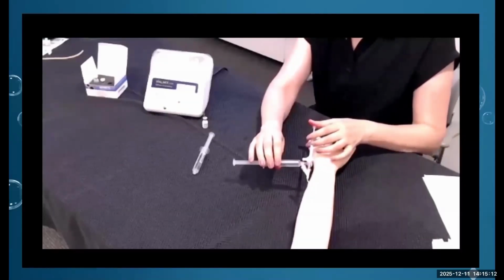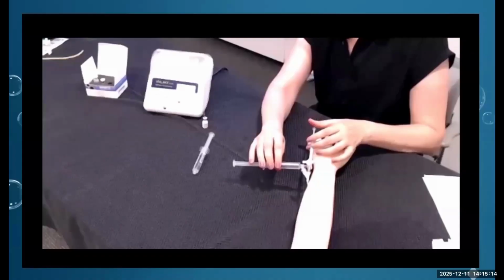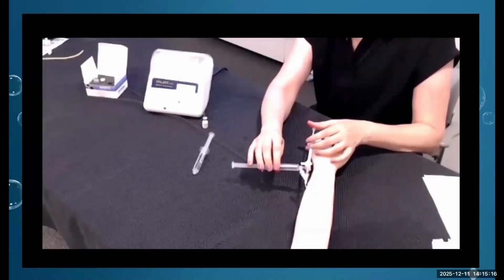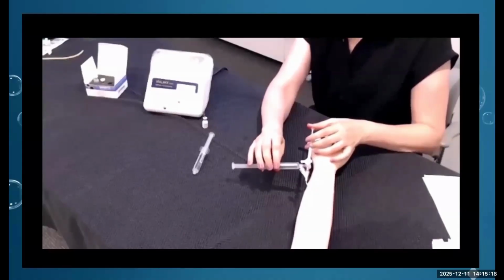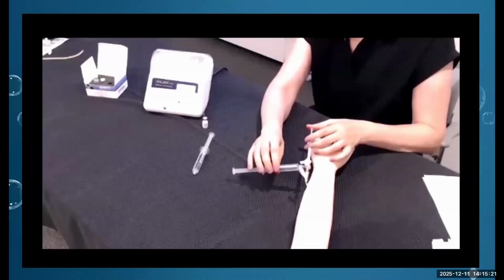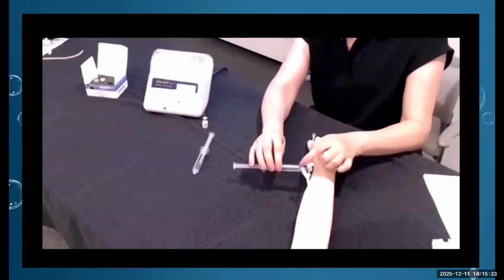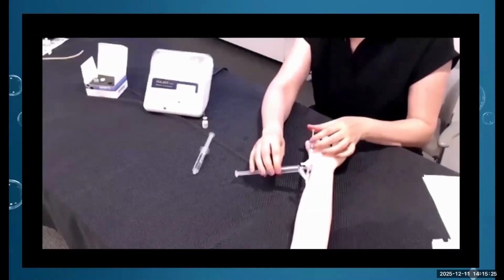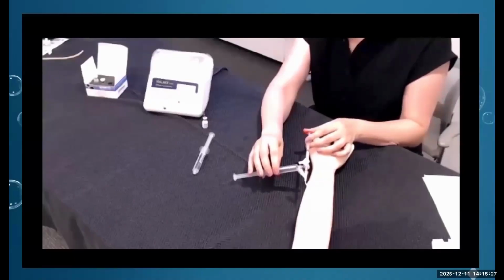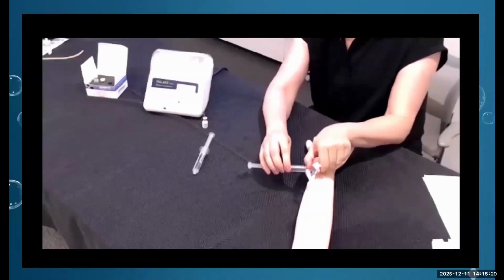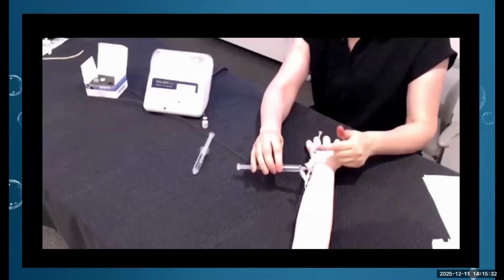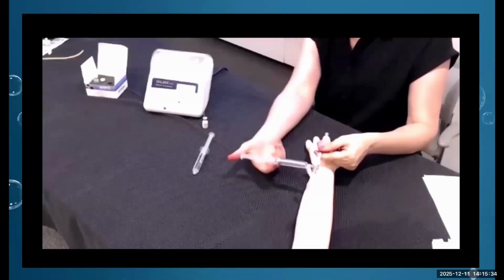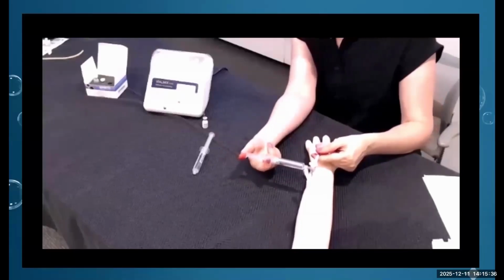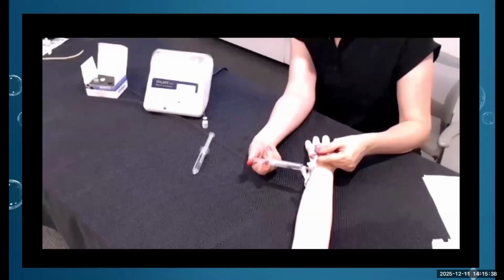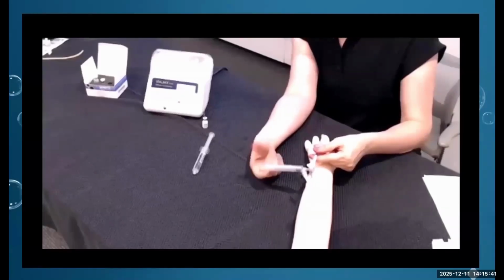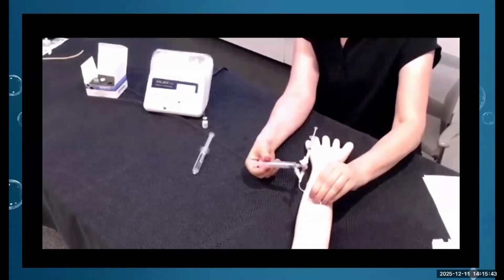Generally for abdominal imaging, the average is 0.2 mL per injection. But for kidney or bowel, we may use a little more or a little less. So the stopcock is now in the off position, facing the saline syringe. You want to inject 0.2 mL of Definity. Turn the stopcock to the off position to the contrast end, and then bolus the saline flush. Then make sure you clamp your tubing.